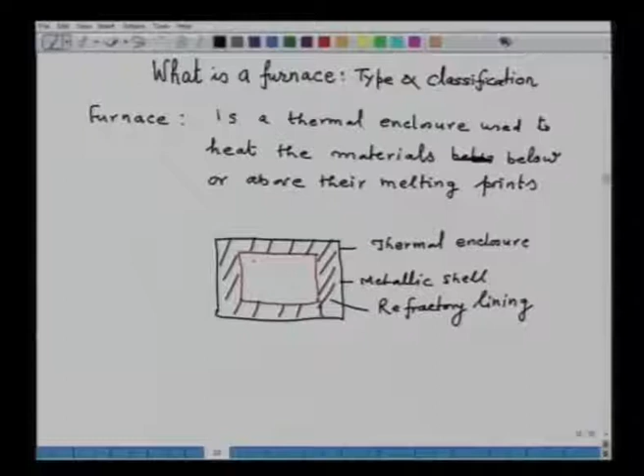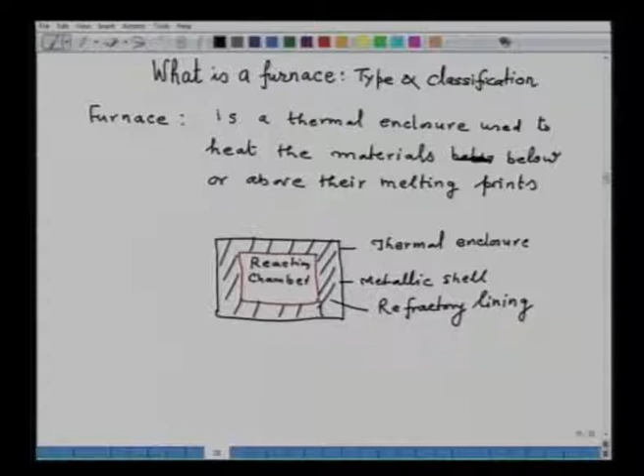Because when we talk of high temperature, the metallic shell, because of its high thermal conductivity and cost, is not used directly. That means it is lined with the refractory material for the conservation of heat. Metallic shell has a very high thermal conductivity, and whatever amount of heat is generated will be immediately lost. So, this one is the reaction chamber.